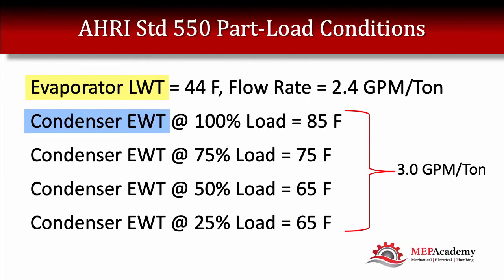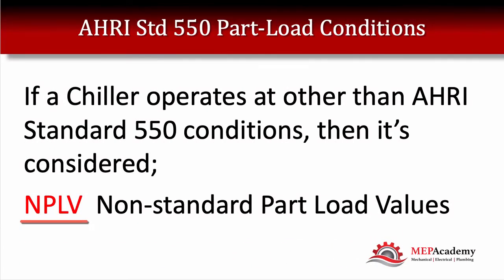What is AHRI Standard 550? These are the conditions under which the standard is developed. At 100% load, the condenser entering water temperature is 85°F, and as the load drops off, the condenser water temperature also drops off. Flow rate is 3 GPM per ton. The evaporator leaving water temperature is 44°F at a flow rate of 2.4 GPM per ton. If a chiller runs at conditions other than AHRI Standard 550, it's considered Non-Standard Part Load Values — NPLV.